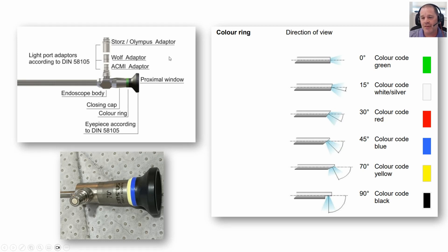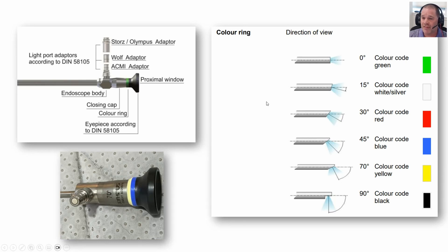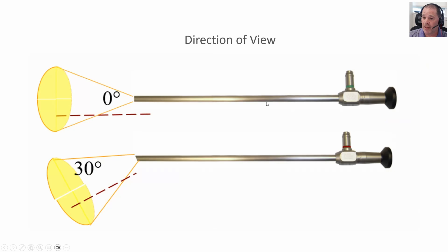It's up to us as companies or OEMs to figure out how to provide education on which ones to use. Sometimes that's a model number nomenclature, sometimes it's a color indicator. This is just one manufacturer's color coding system to determine the angle of view of a scope. For those not familiar with rigid endoscopes, they come in different shapes and sizes — lengths, diameter, and angles of view. A traditional endoscope will look straight ahead, and some work in the 30-degree spectrum.